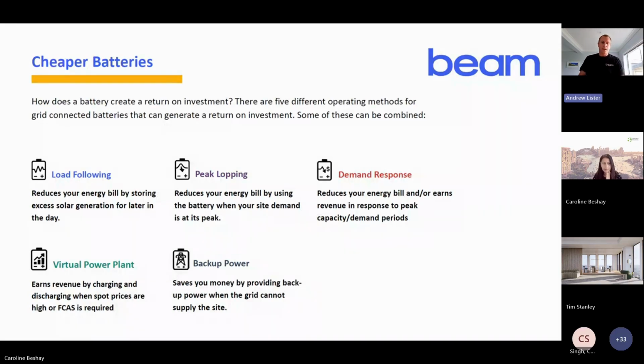The second operating method is called peak lopping or peak shaving. Under this methodology, the battery charges when your demand is low and discharges when your demand is high, bringing your maximum monthly or annual demand down, which saves on demand charges.